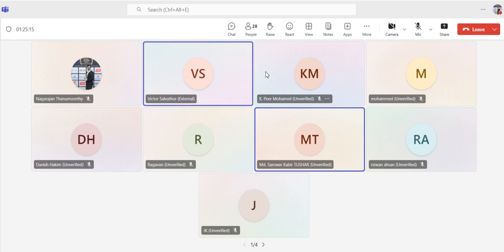So sir, for the secondary pump I have to consider from chiller to load, and for the primary pump, load to chiller. Yes, but always you need to consider the loop, because it's a loop system, right? Otherwise, you have to provide static. We are calculating only the pressure. I'm repeatedly saying we are doing the calculation of a pressurized system, not an empty one. When we do the pump calculation, it means the line is already pressurized.